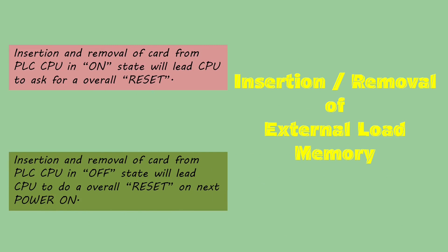One important thing about expansion of load memory is: if we insert or remove an expansion load memory card — either flash or RAM type — when the PLC is in the on state, it will ask for an overall reset. But if we insert or remove the memory card in PLC off condition, the PLC will automatically perform an overall reset on the next power-on.